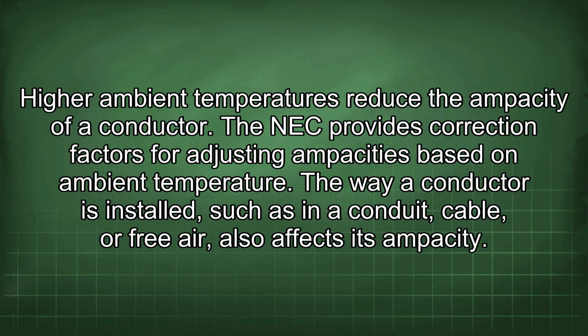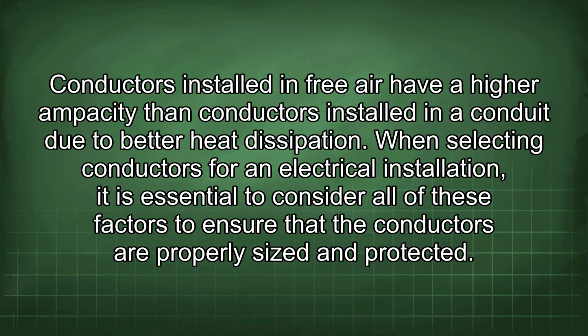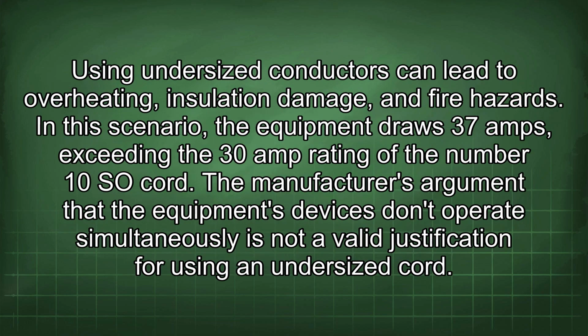Higher ambient temperatures reduce the ampacity of a conductor. The NEC provides correction factors for adjusting ampacities based on ambient temperature. The way a conductor is installed, such as in a conduit, cable, or free air, also affects its ampacity. Conductors installed in free air have a higher ampacity than conductors installed in a conduit due to better heat dissipation. When selecting conductors for an electrical installation, it is essential to consider all of these factors to ensure that the conductors are properly sized and protected. Using undersized conductors can lead to overheating, insulation damage, and fire hazards.